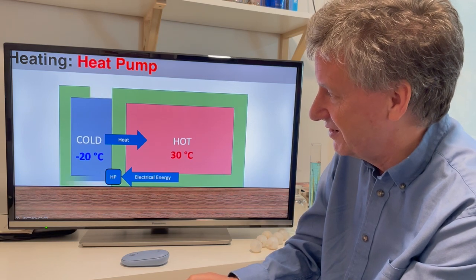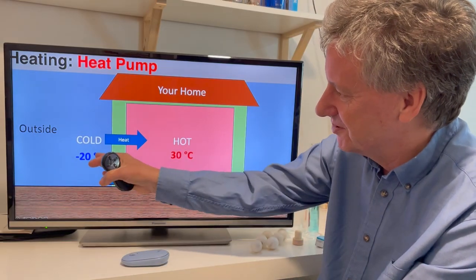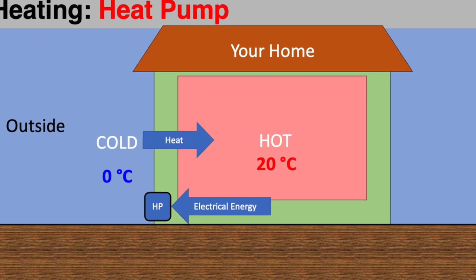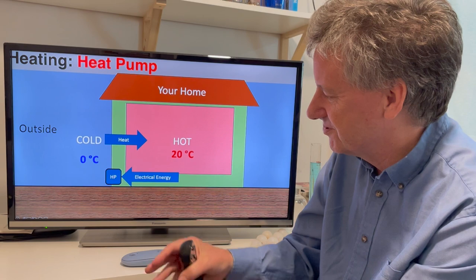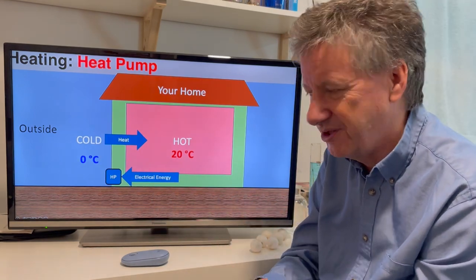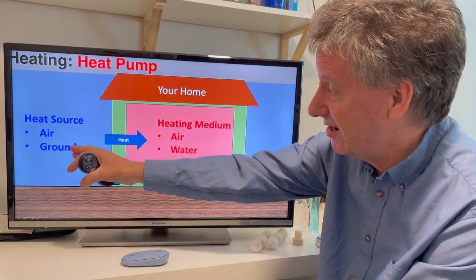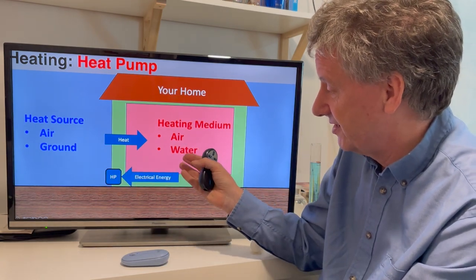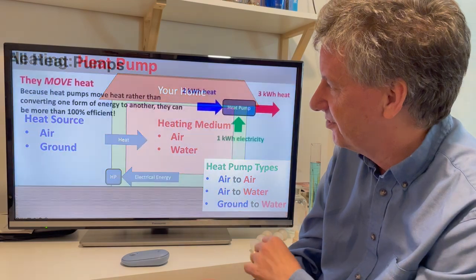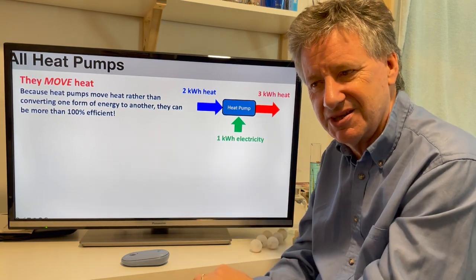When we're talking about heat pumps in a domestic heating arrangement, instead of focusing on making things cold, we concentrate on the hot bit. We put the insulation around the hot bit and take it away from the cold bit — it's still the same heat pump doing the same thing, but now we put the cold bit outside our house. We only want it to go to 20°C inside, and outside is typically 0°C on a very cold day. So heat pumps are doing exactly what they've done in refrigerators for years — the cold bit is now outside; we take heat out of the cold air and bring it inside to warm our homes. We can take heat from air or ground and heat the air or water in our homes. Different types include air-to-air, air-to-water, and ground-to-water.